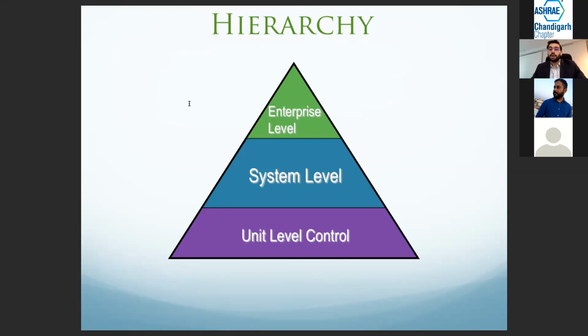Now, all these unitary controllers are around the building, but you need a central brain to control all the equipment and make it work as a system, which is why the system level controller comes in. And there are cases, for example a university, where you may have multiple buildings. In that case, you may have an enterprise level, whereas each building may have one or more system level controllers, depending on how many points there are. All of them are grouped together in one central place where you log in and can see all your buildings instead of having to log into each building every time.